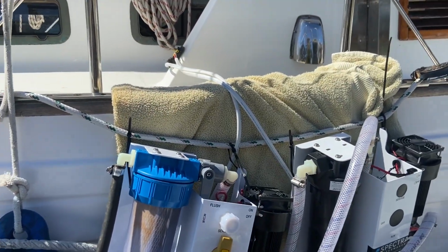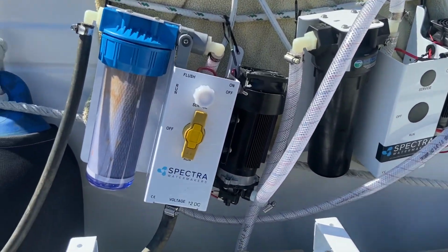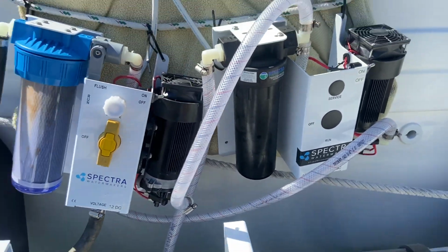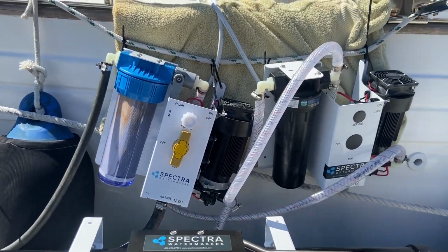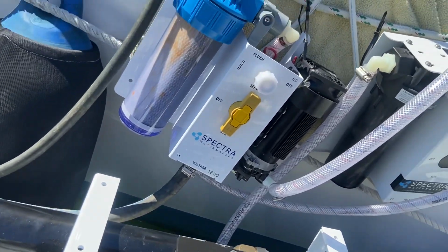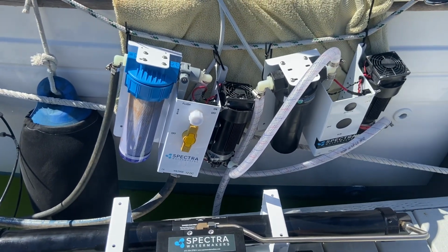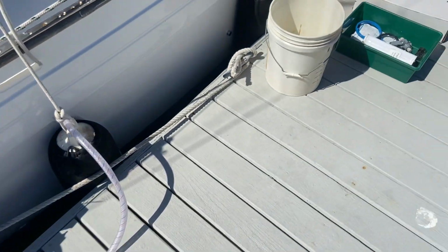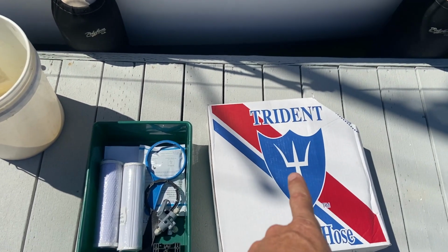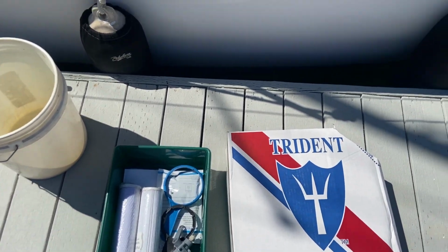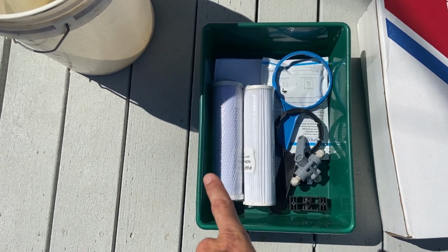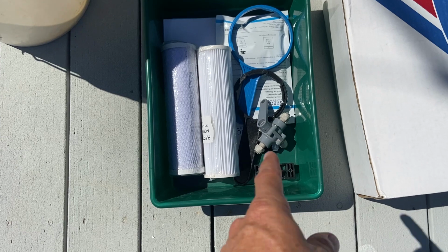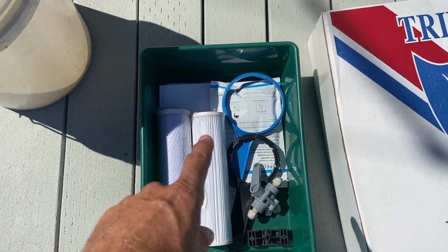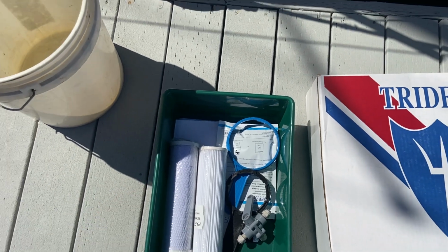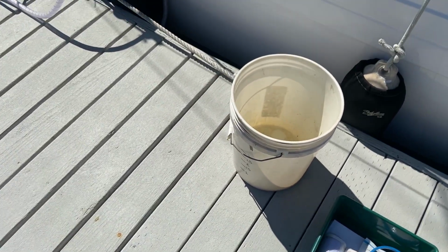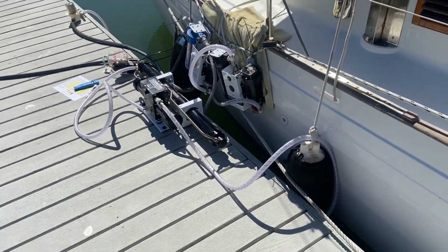I measured with a clamp meter. They're drawing 8 or 9 amps each, so right within spec. Also notice how quiet this system is. I mean, you could easily carry on a conversation right here, and it's fine. And these systems are usually in a locker or down below deck, so very quiet. So also with this system, you get 50 feet of reinforced 5/8 hose, charcoal filter, 5 micron filter, your filter wrenches, 3-way valve, some SC1, a TDS meter that I was just using, a manual, and then of course the service kit and the install kit, which is mostly in use on my test bench here.